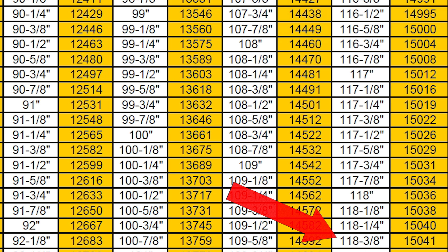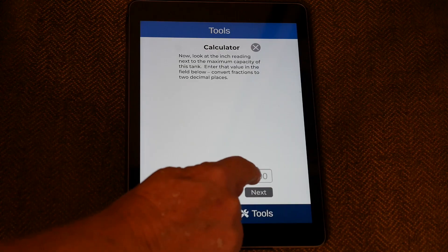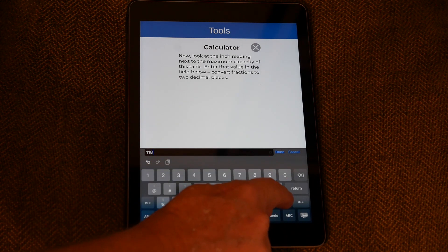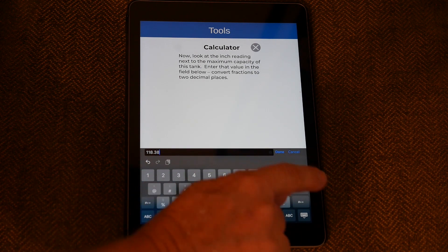Look at your tank chart and find that 15,041 maximum gallonage to see what the inch reading is for that. According to this chart, it's 118 and three-eighths. We need that in decimal format, so three divided by eight gives 0.375 — I'll round up to 0.38. So the inch reading I enter is 118.38, which is the inch reading at that maximum amount. Then the calculator gives me the value I need to look for on the tank chart.